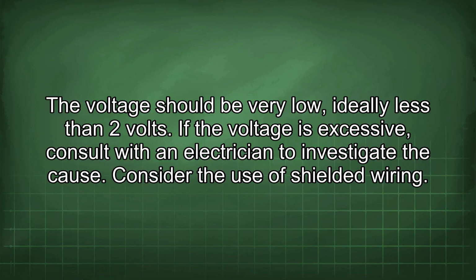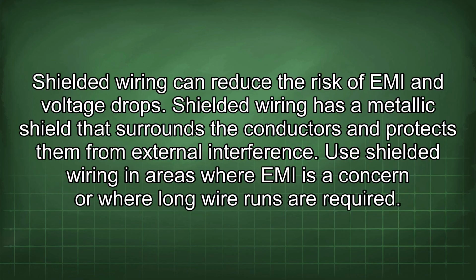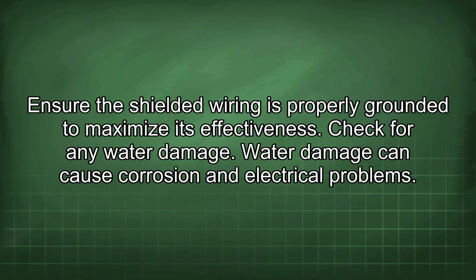Consider the use of shielded wiring. Shielded wiring can reduce the risk of EMI and voltage drops. Shielded wiring has a metallic shield that surrounds the conductors and protects them from external interference. Use shielded wiring in areas where EMI is a concern or where long wire runs are required. Ensure the shielded wiring is properly grounded to maximize its effectiveness.